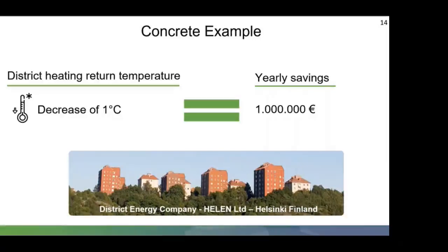The decrease of 1 degree on the return temperature, they have created a yearly saving of €1 million. And that's just 1 degree. In Helsinki, they encouraged increased delta T and efficient systems by adding price support to the energy on top of added savings detailed in the example. So they're quite keen on getting everybody on board, and by using smart controls and monitoring the system from the beginning to the end, there's a way of reducing the district heat temperature return and making the buildings more efficient and the heat network more efficient.